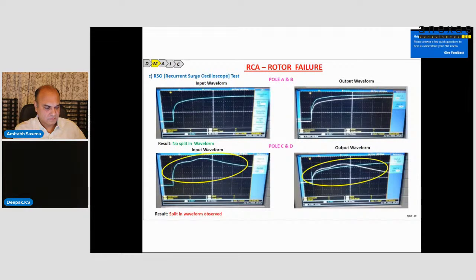Further, we did a test called the recurrent surge oscilloscope, RSO, test, where we can see the input waveform. I think you can see in the slide the input waveform and output waveform. Since poles A and B are okay, you can see the input waveform and output, but there is no split. If you come to the next, C and D poles, you can see there is a split in the waveform. So this indicates that there is an interturn short or the rotor has failed. This gives an indication.